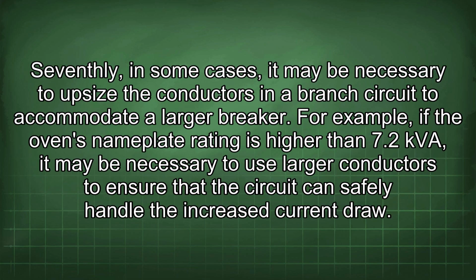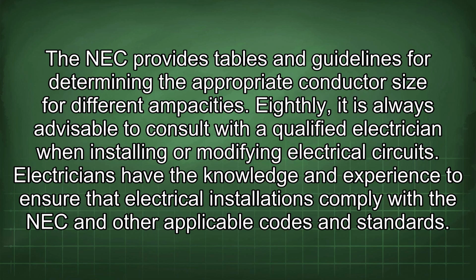Seventhly, in some cases, it may be necessary to upsize the conductors in a branch circuit to accommodate a larger breaker. For example, if the oven's nameplate rating is higher than 7.2 kVA, it may be necessary to use larger conductors to ensure that the circuit can safely handle the increased current draw. The NEC provides tables and guidelines for determining the appropriate conductor size for different ampacities.